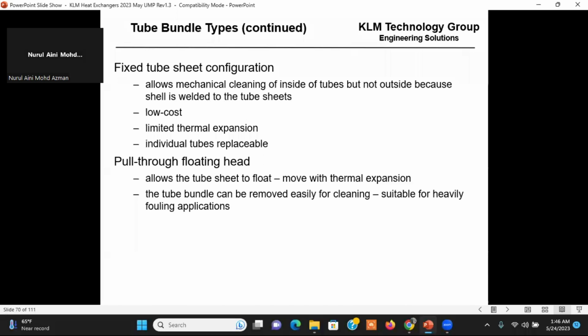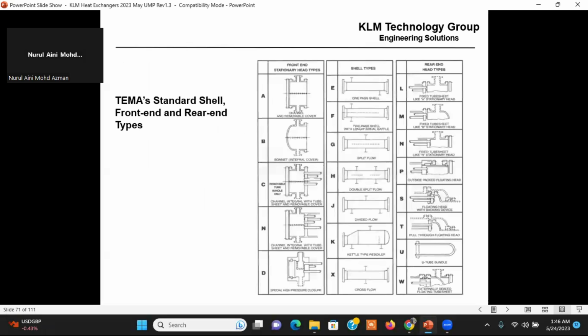Two tube sheets. Got to be very clean surface. It allows mechanical cleaning of the inside of the tubes, but not the shell because it's welded to the tube sheets. It's low cost, with limited thermal expansion. Individual tubes are replaceable. Pull through floating head. Occasionally, I'll use a pull through floating head. It's able to move with thermal expansion. Tube bundles can be removed. Easy for cleaning. All right, and here's TEMA specifications.